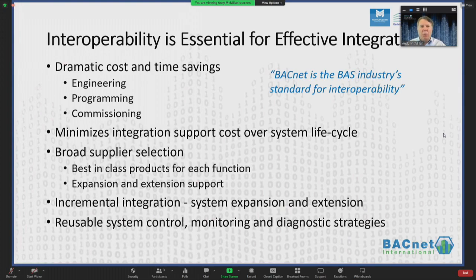You also get a broader supplier selection when dealing with an interoperable BACnet world, which means you can pick the best product in each class regardless of supplier. And when you put in a system, and come back in two years wanting to extend or expand it, you can do that without custom integrations between the vendor who did the first one and the vendor who does the second.